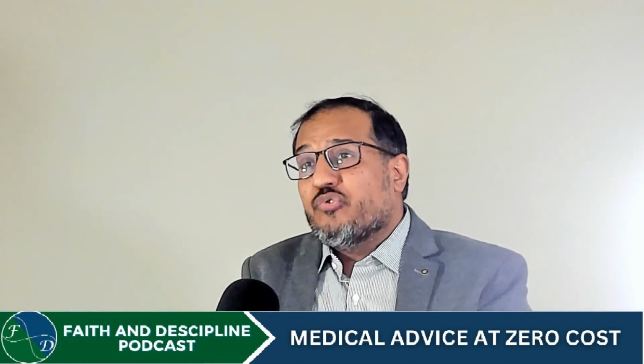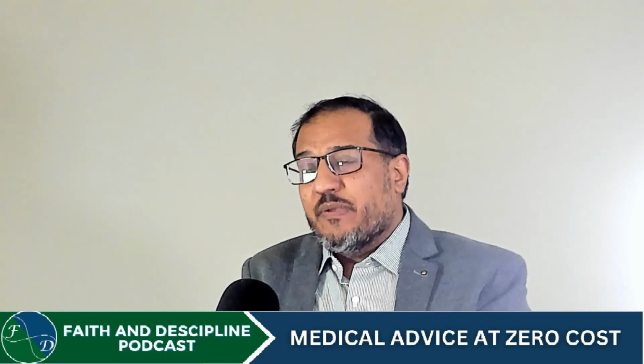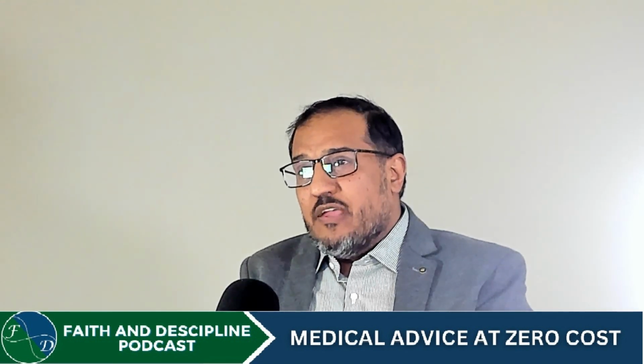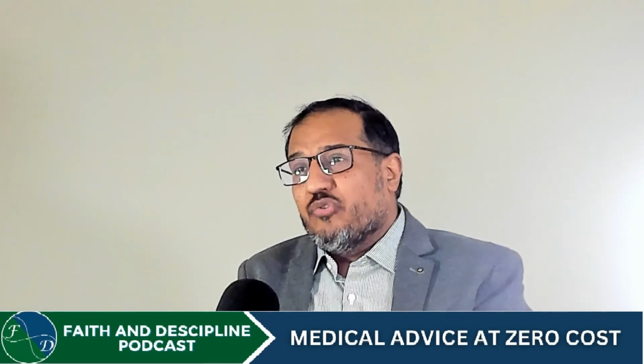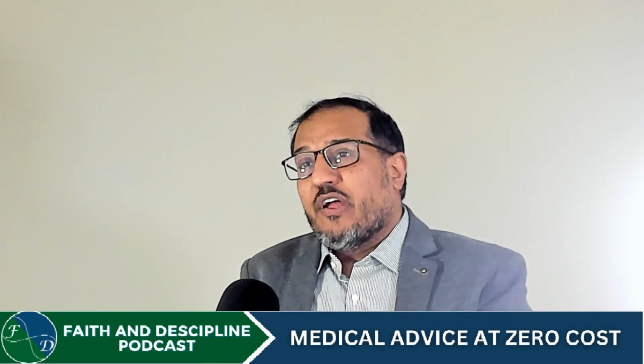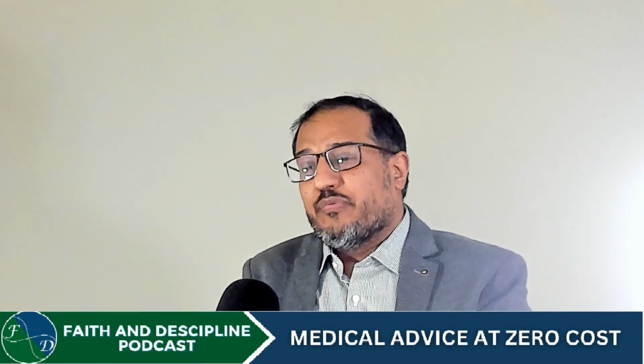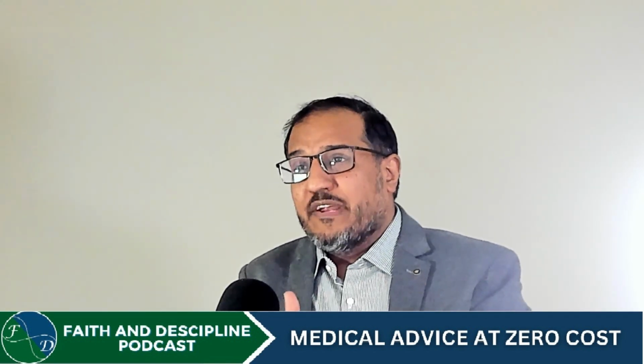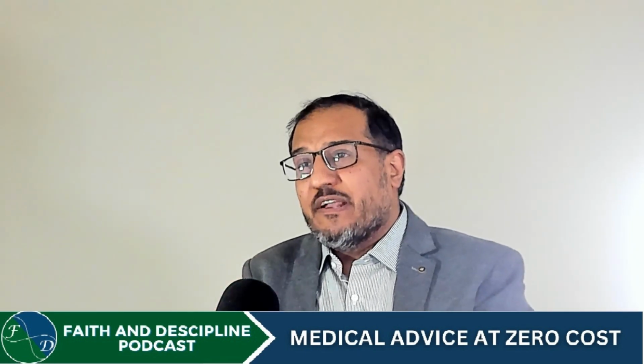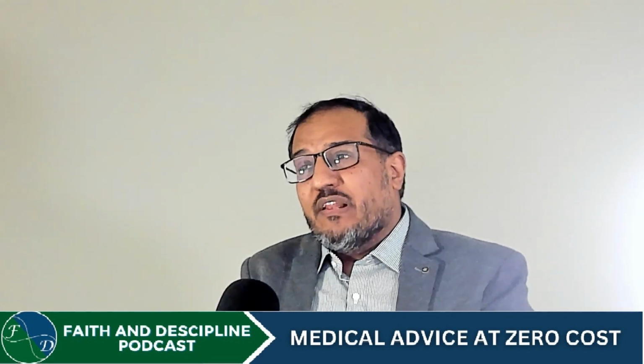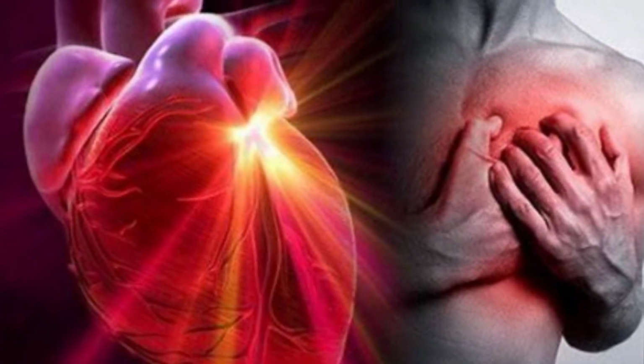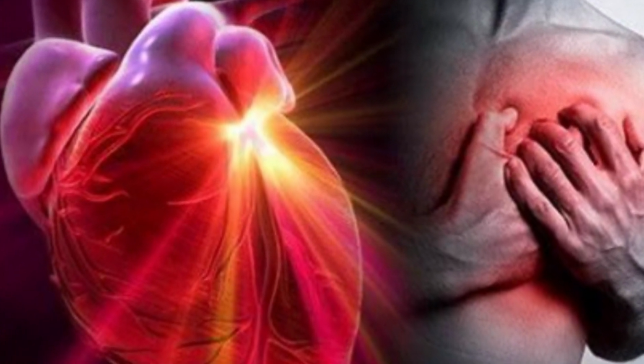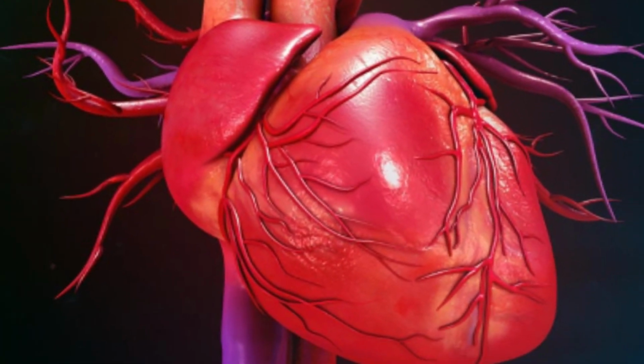Normally, it depends upon the usage of the pacemaker. For example, if 90% or 95% of the daily heart beating is dependent on it, we call it pacemaker dependent. If the heart is dependent on the pacemaker and it uses the battery 24 hours, the battery will deplete quickly, but normally it takes 5 to 7 years in that case. Okay. So the patient comes back after 7 years to get it replaced.